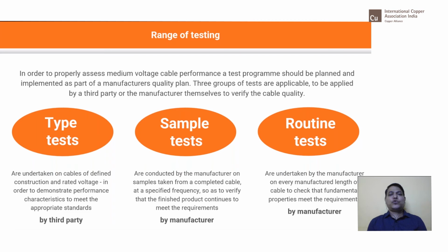When it comes to sample test, it is basically undertaken on a representative number of cable samples, which will be agreed as a part of the contractual quality plan with the contractor or a purchaser or utilities. We call it also FAT, which is a factory acceptance test, where certain kilometers or certain types of cables are produced and offered for inspection. Then the third party inspection body or the end user selects a random sample from the quantity offered.